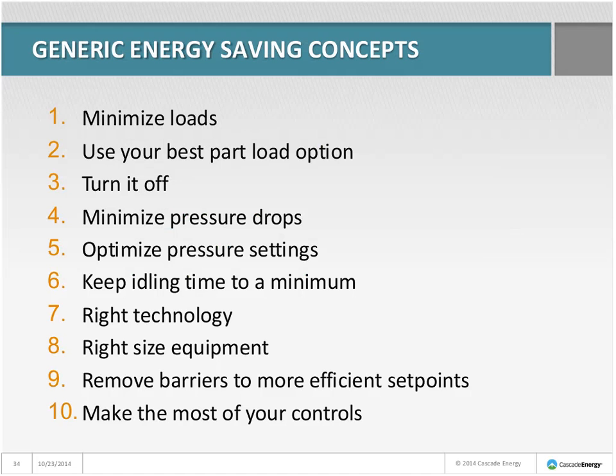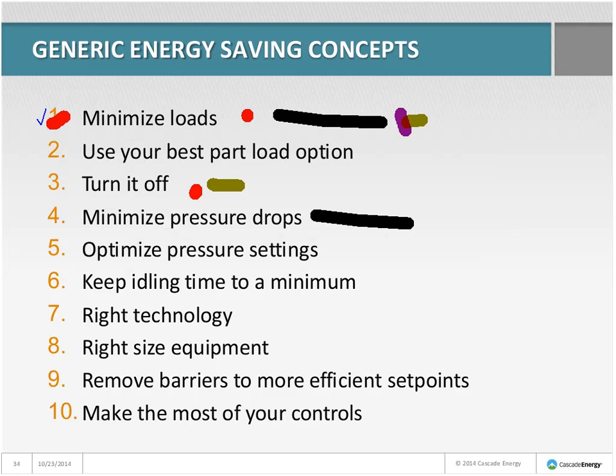Which concepts did the beverage bottling plant take advantage of? Minimize loads — this was all about getting users off compressed air or figuring out how to use less. And right technology — using the right technology to use less compressed air or no compressed air at all.